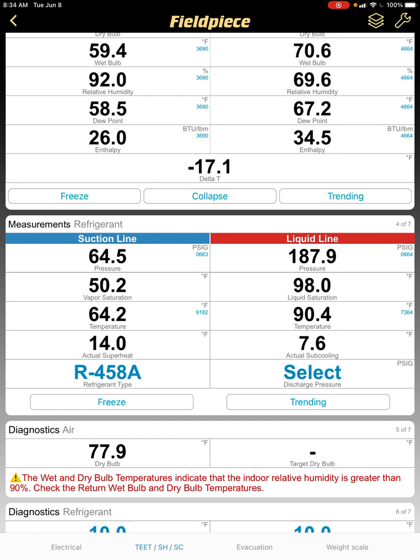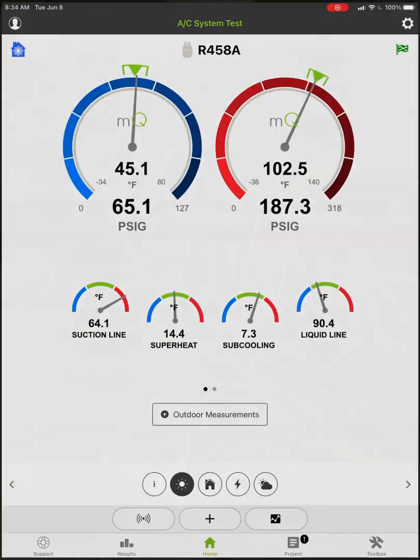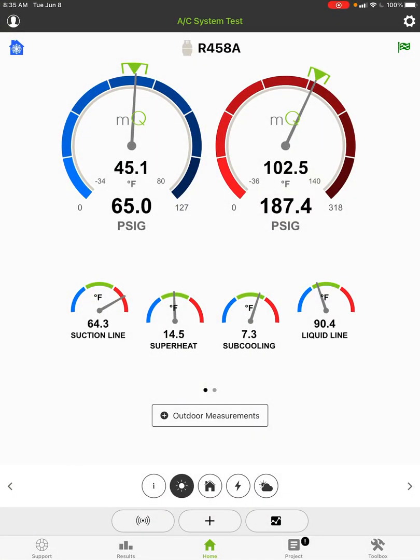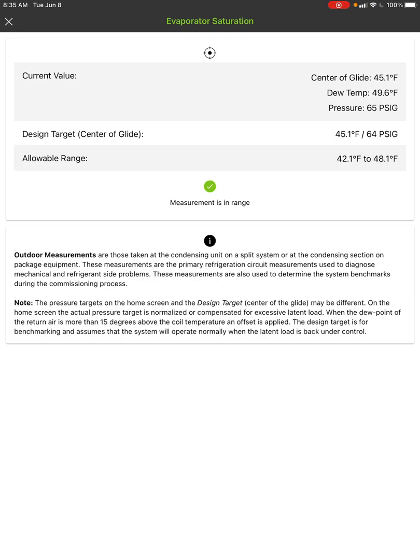So why is this the case? MeasureQuick does some things different than most other apps because we're doing them the right way, which is to show you the dew point and the bubble point instead of the average coil temperature. An easy way to remember it is 'duperheat and bubcool' — we use dew point temperature for calculating the superheat, and bubble point for calculating the subcooling.